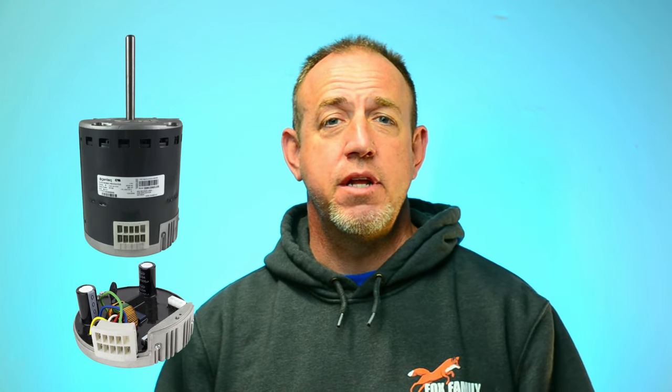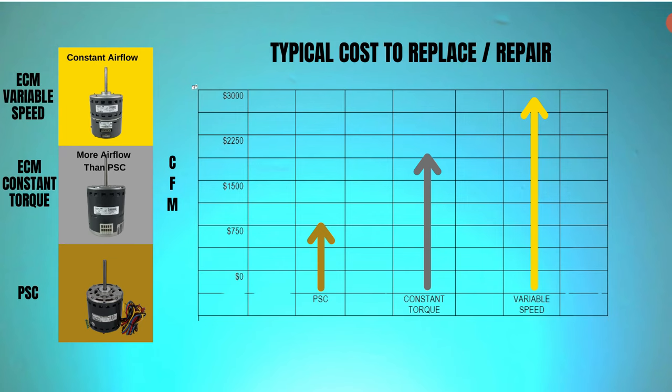ECM constant torque motors — the most familiar name is the X13 by Genteq. Genteq acquired GE's Motors and Capacitors Division in 2004 and renamed themselves Genteq in 2009. The first high-efficiency residential HVAC ECM motors were made by GE back in the 1980s. These motors use an integrated control board to send the signal for operation and what speed or torque setting to run at, making them more expensive than PSC motors, though not as expensive as variable speed motors. X13 motors were designed in 2006 to achieve higher SEER ratings — specifically the 13-SEER standard, thus the name X13.